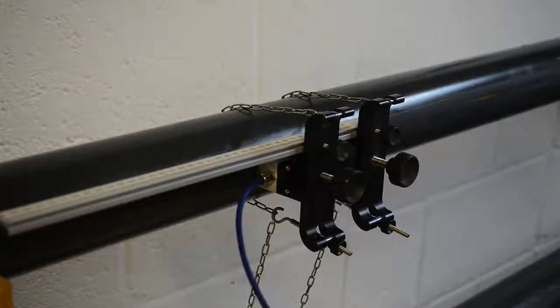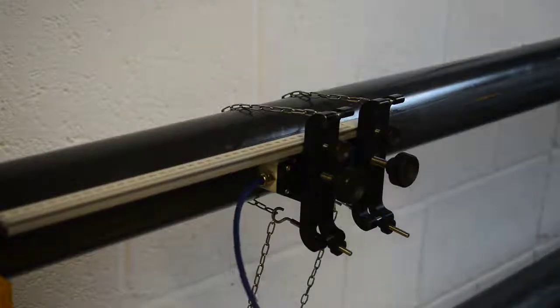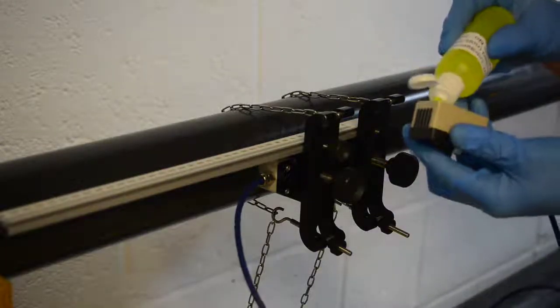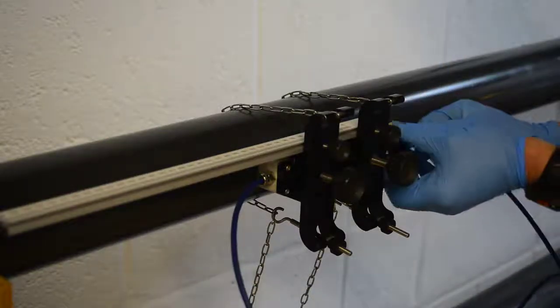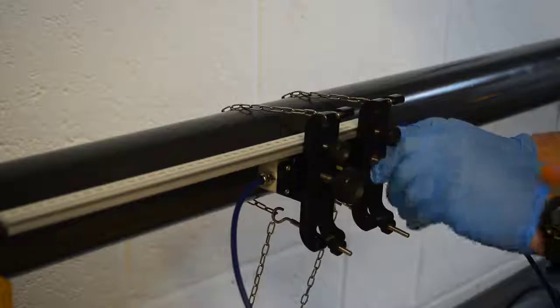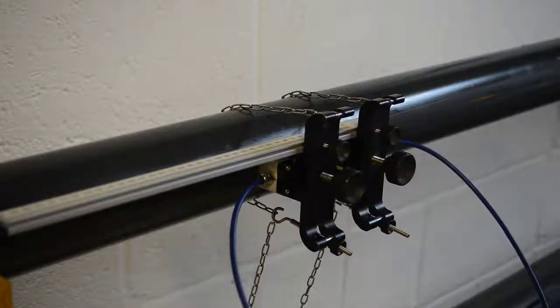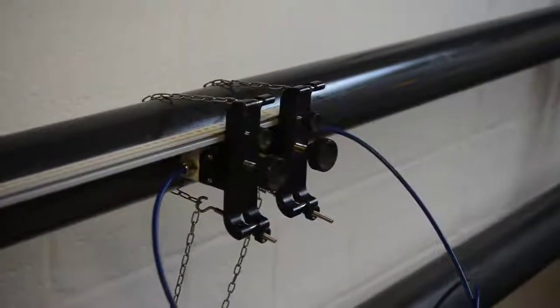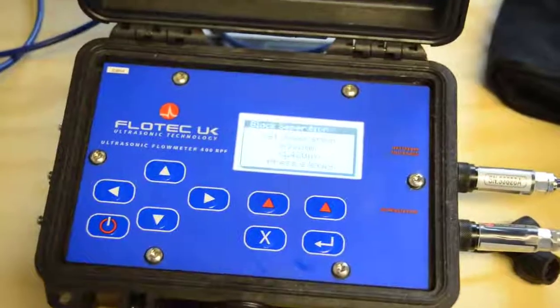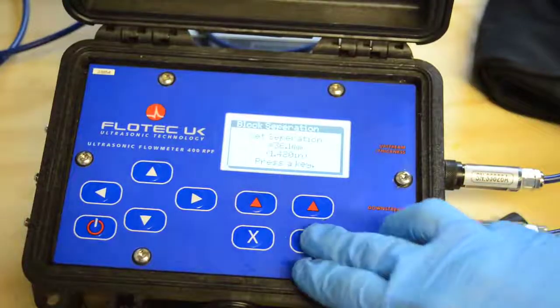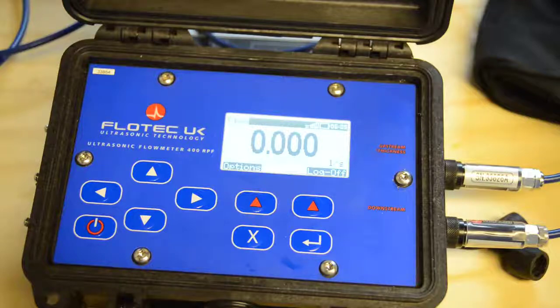On the flow meter, it's clearly marked upstream and downstream, so I'm placing this into the upstream connector, and we repeat the procedure of couplant. One into the downstream connector, and that's the setup done really. So now when we're happy with that, we just press enter, measure flow, and there we are. We're in the main flow screen now.